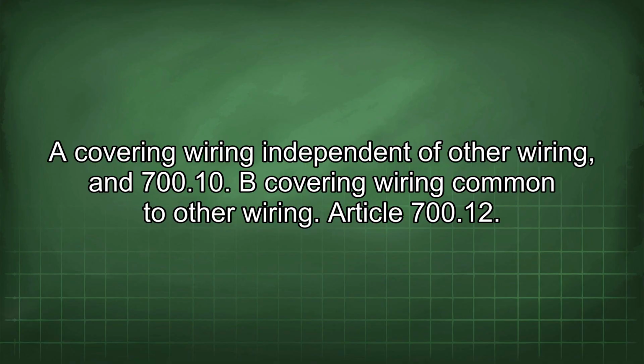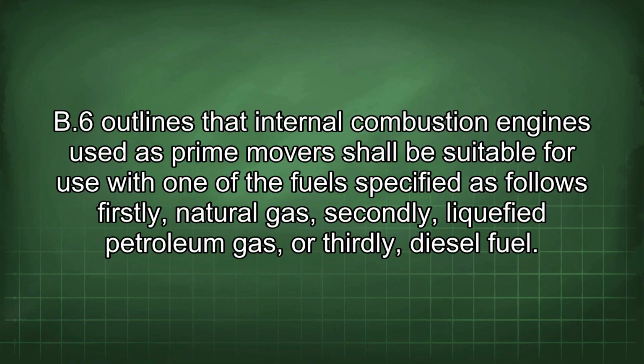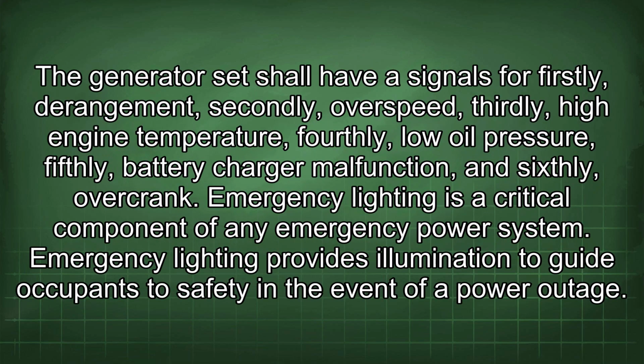Article 700.12(F)(2) outlines that internal combustion engines used as prime movers shall be suitable for use with one of the fuels specified as follows: firstly, natural gas; secondly, liquefied petroleum gas; or thirdly, diesel fuel. The generator set shall have signals for firstly, derangement; secondly, overspeed; thirdly, high engine temperature; fourthly, low oil pressure; fifthly, battery charger malfunction; and sixthly, overcrank.